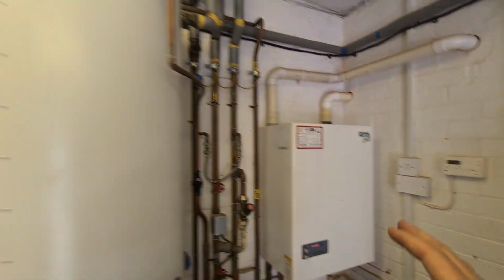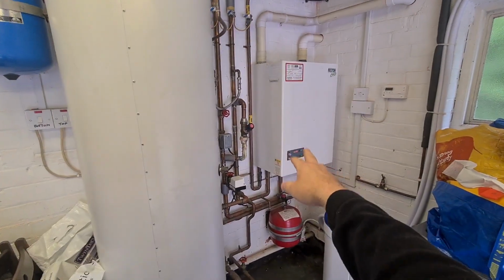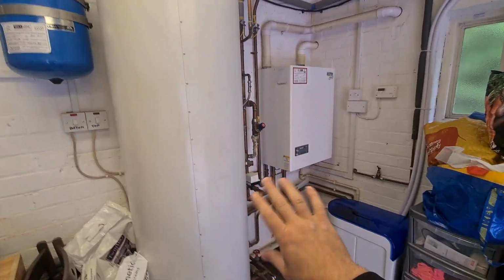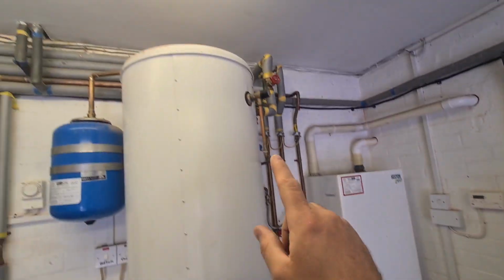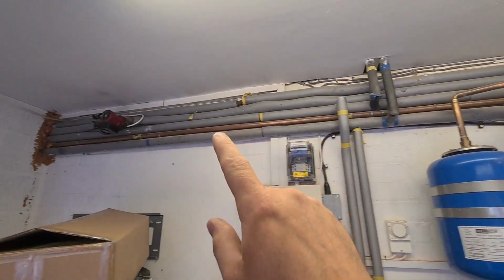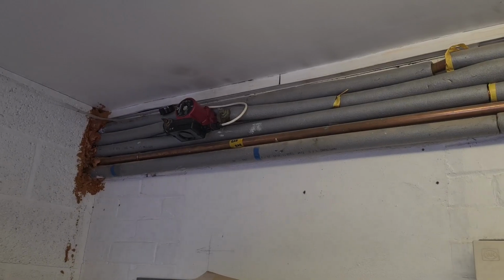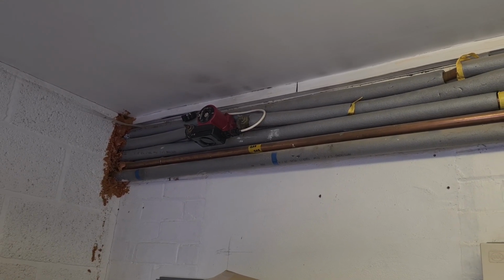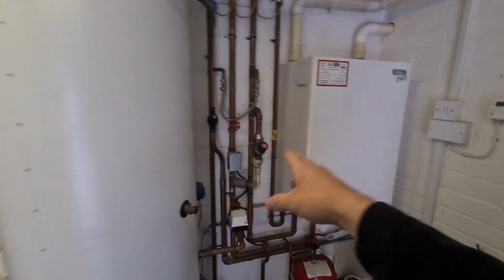But what really bugs me about this is, this boiler, bear in mind, has got a 25/70 pump in it. There's no low loss header installed, no nothing. If we follow the pipework along the top there, someone thought it was a good idea to slap another pump on the heating. So again, we end up with pump pressure and balance issues on the system. So I've got a 25/70 inside this Keston behind me, trying to do what it needs to do, with a 25/80 sat up there, which again is just going to create cross circulation on everything on the system.